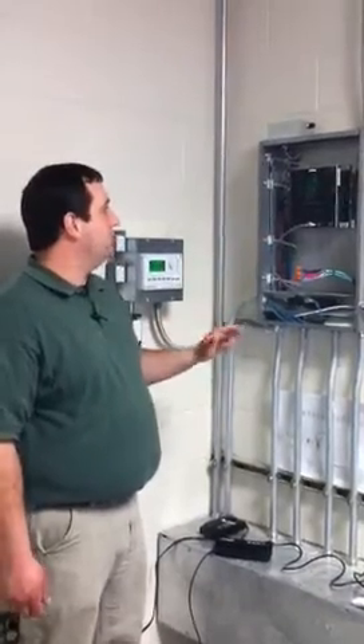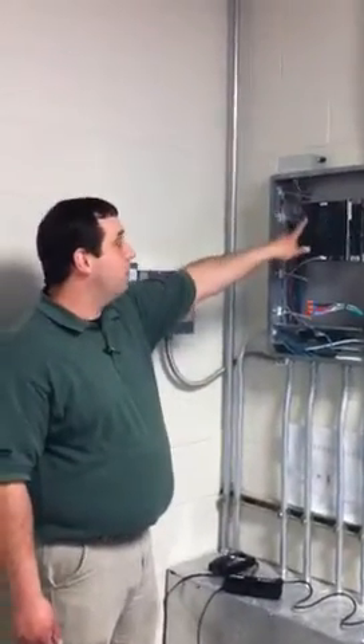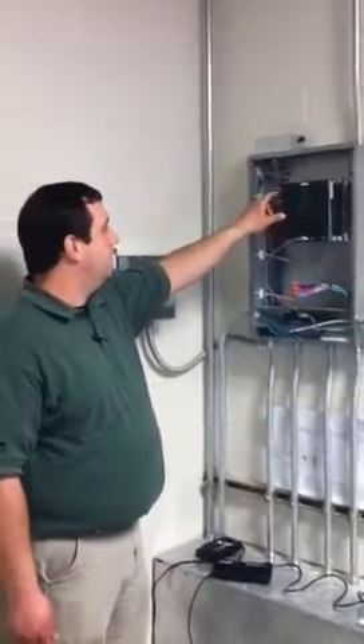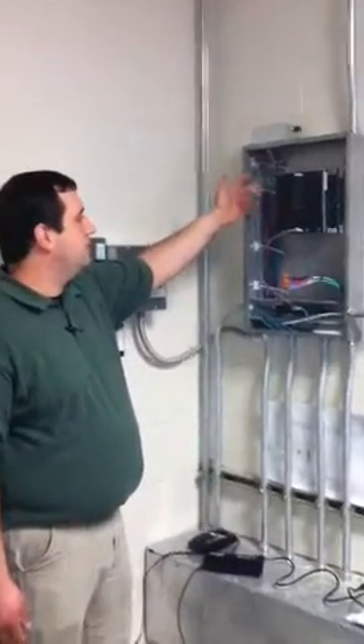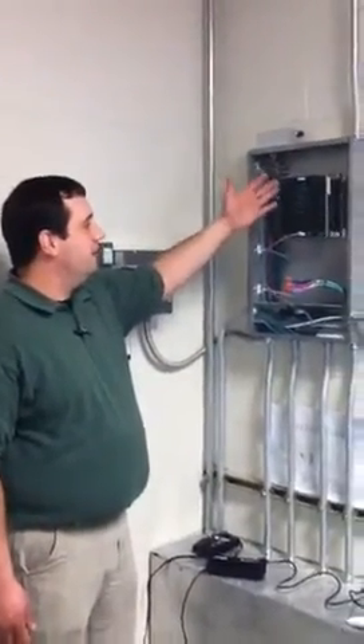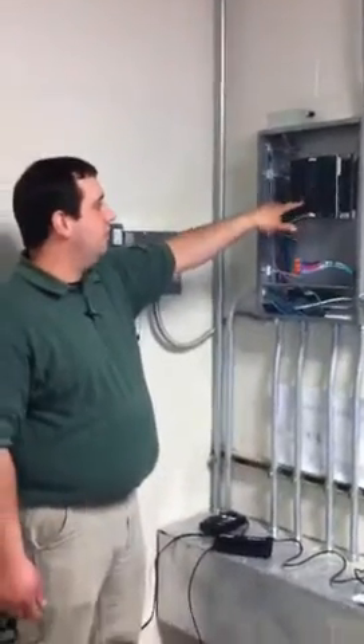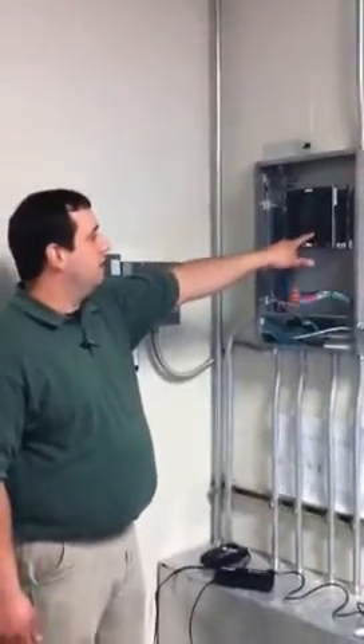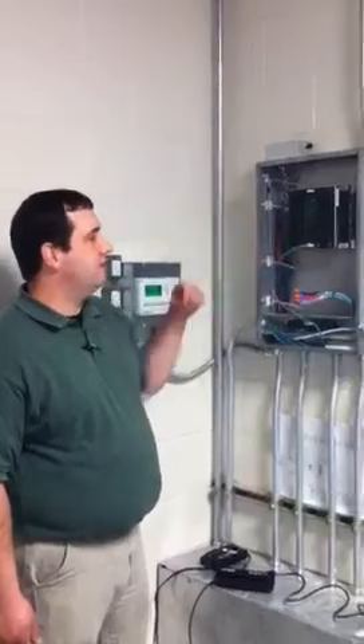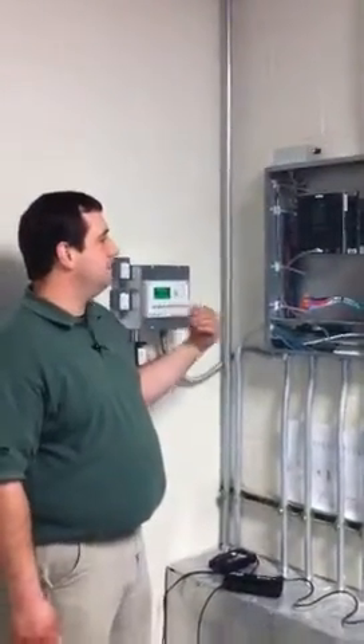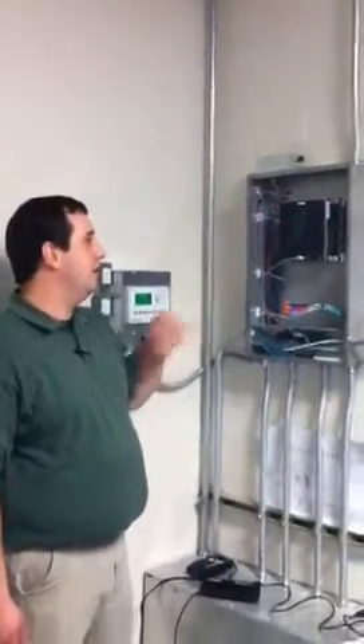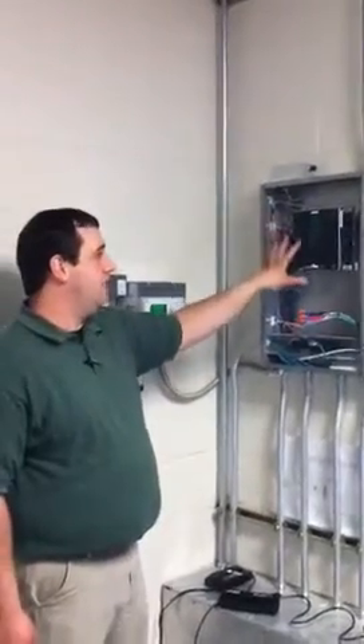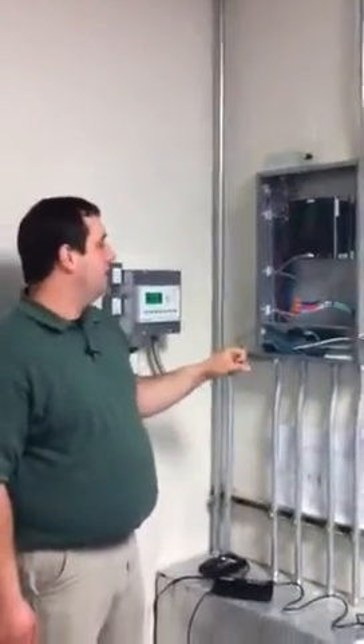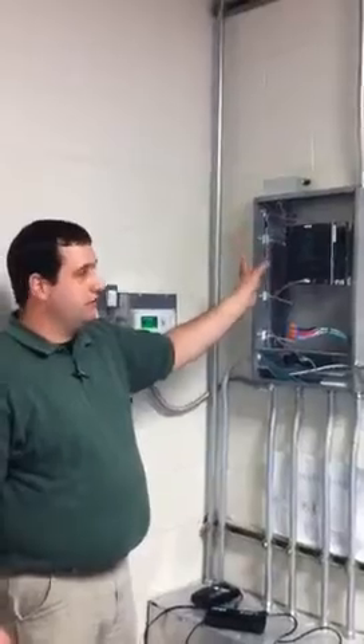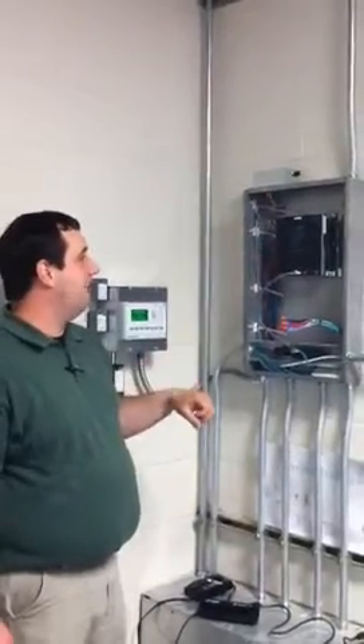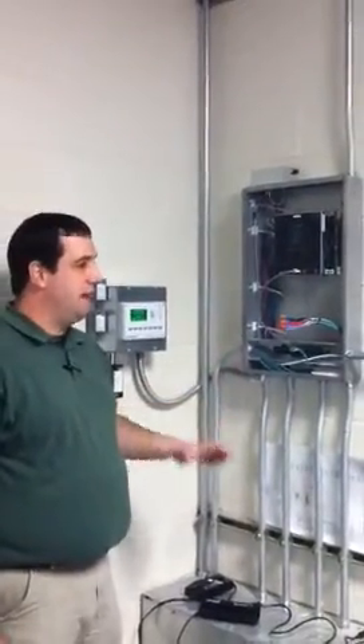Basic things to troubleshoot is that the module itself is powered out of input 1. Basically, in this case, it's 120 volts. To check if the system is functioning, basically the window will be lit up, and there's a power light and a net light. The net light basically means that it is communicating with the system. If the net light is off and the lights are not working, it's possible that the ID has changed or there's a problem in the unit. Aside from that, there are no user serviceable parts inside, and everything else is handled from the factory.